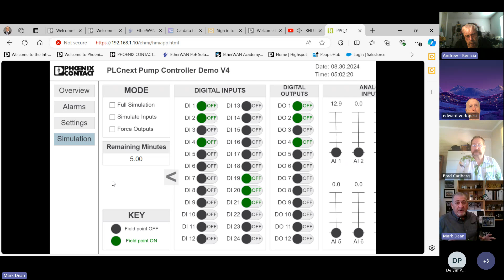These are the screens that do not need to be programmed, only configured. I hope by going through that I've shown how easy it is to configure this. If you guys were to set up a pump controller in your plant floor demo at WSU, you could put this pump controller online pretty quickly. Then I would take data from this and use it to create some screens on top of it. That could be a pretty interesting project.